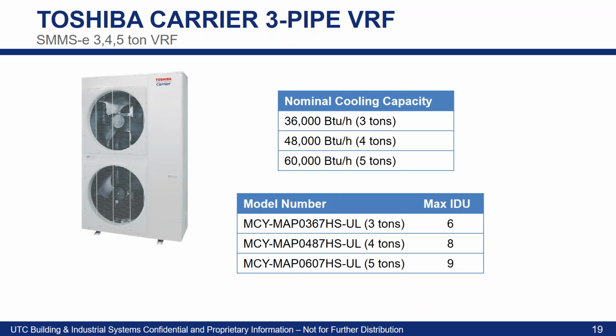So connected capacity, Sean, is where you have a nominal capacity on your outdoor unit, right, or your VRF condensing unit. Now, your connected capacity is going to be your nominal capacity of indoor units or VRF fan coils, okay? You're going to compare that versus what you have on the nominal outdoor side. So let's say you got a 5-ton unit and you're hanging more than 5 tons off of it, your connected capacity is going to be over 100% because you've exceeded that 5-ton nominal outdoor unit capacity, which is fine, but it's all application specific. So we got to be careful. We got to know what we're serving, most importantly.